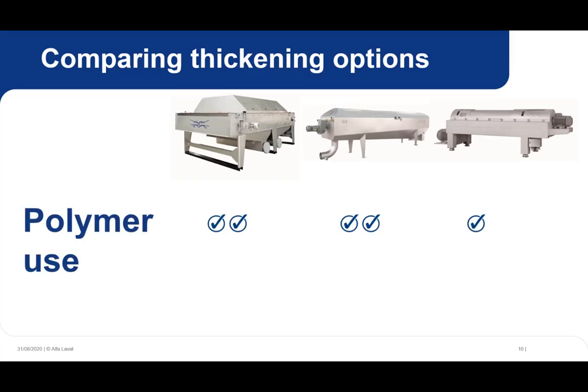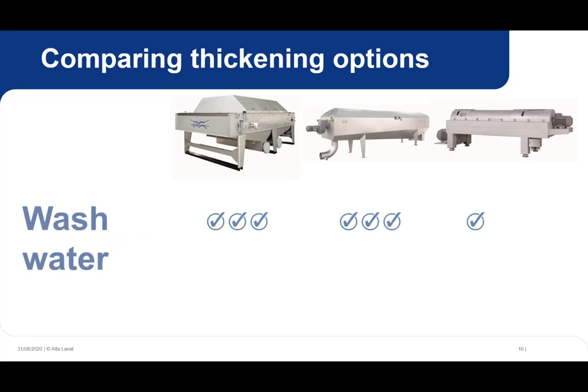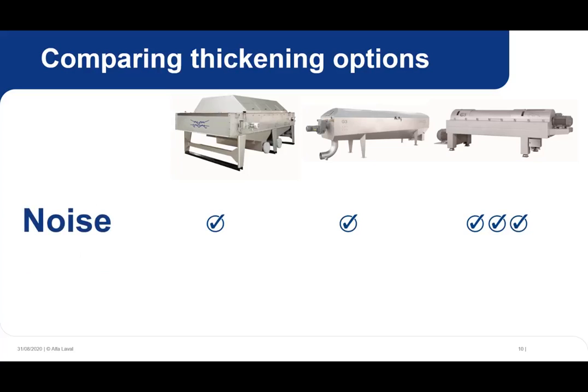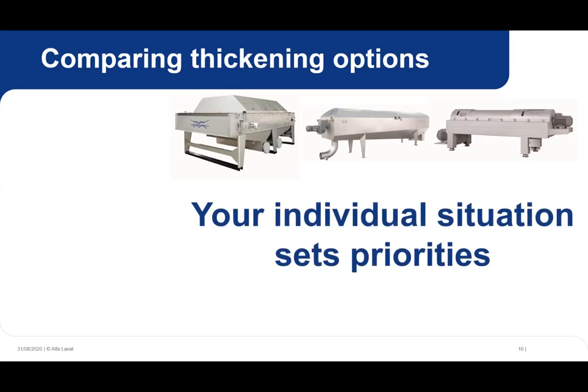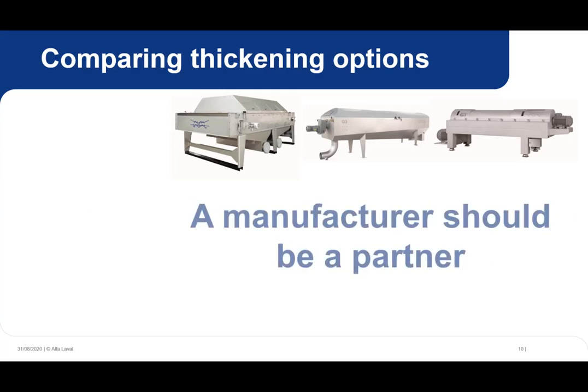Polymer use in thickening is relatively close, but some new advances in centrifuge technology can give it an advantage over other equipment. The belt thickener and drum thickener require higher amounts of wash water versus a decanter centrifuge, but because of the high-speed operation of the centrifuge, it is the noisiest of the three technologies, which for some may be a consideration. Your individual situation and requirements will help determine which of these priorities matter the most. And your manufacturer's role is to listen, help evaluate your needs, and to provide options so you can make the best decision for your specific situation. Now let's talk about an innovation in thickener technology.